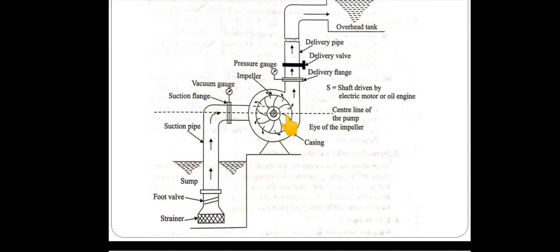So what is cavitation? Cavitation is nothing but the erosion or corrosion which takes place on the impeller. Here, due to negative pressure, usually water comes at room temperature, let me take 27 degrees centigrade. What happens? Due to this rotation, the pressure here decreases. So this leads to vaporization or boiling of water when the cold water comes here. How does boiling take place?